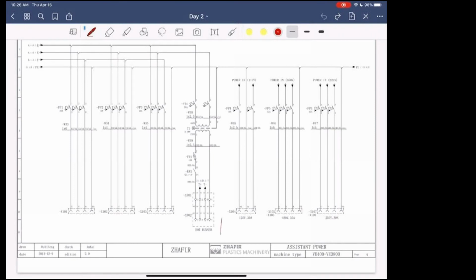This is the optional hot runner circuit. Again, it has another transformer. It'll be a T3 transformer, which is 33.5 kilowatts, depending on the size of your heater circuit, your hot runner circuit. And these are options also, if you want 220 volts or whatever.